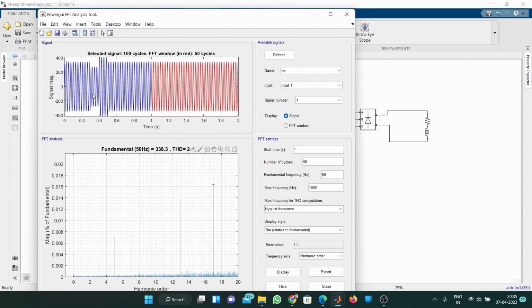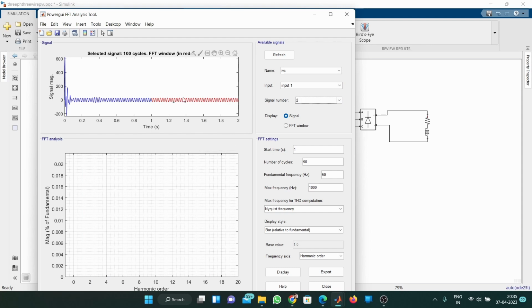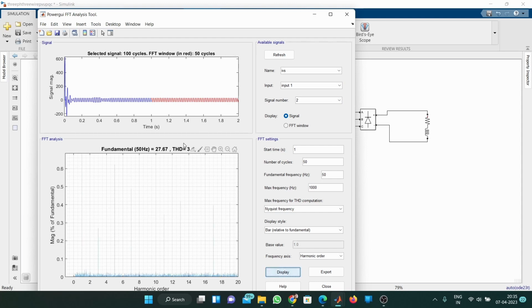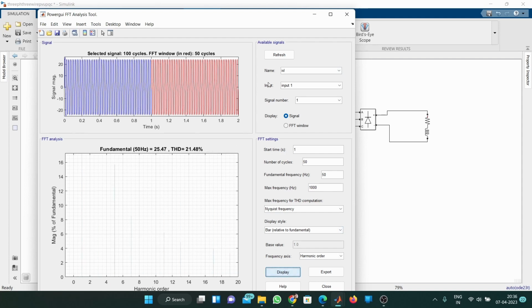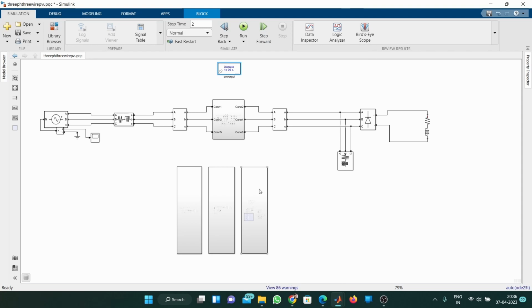You might be seeing here a dip and swell in the voltage level. I will show you later. Sorry, I have shown the voltage analysis earlier. I will show you for the current. Here you can see that the THD in the current is reduced to 3.34%, and in the load current it was around 21.48%. So there is a reduction in harmonics. I have shown you three things: the reduction in harmonics, making the load current balanced on the source side, and the reactive power compensation by showing you the in-phase voltage and current of the source side.